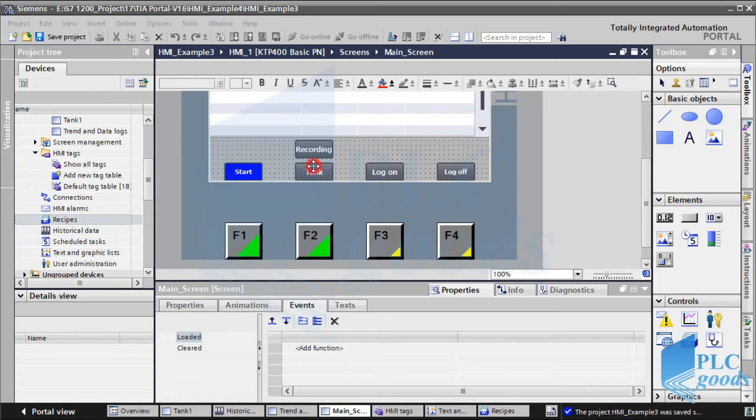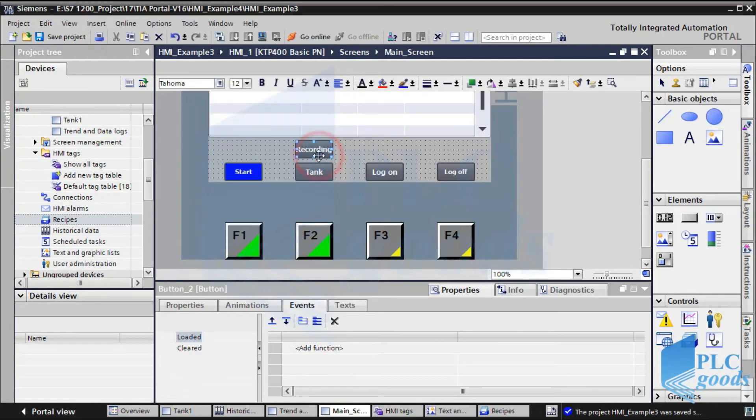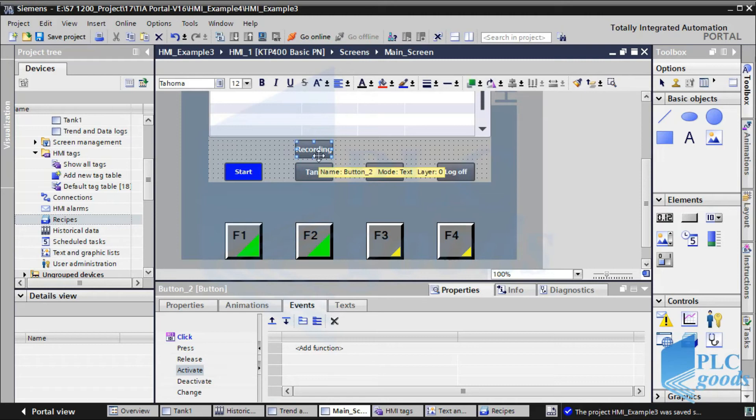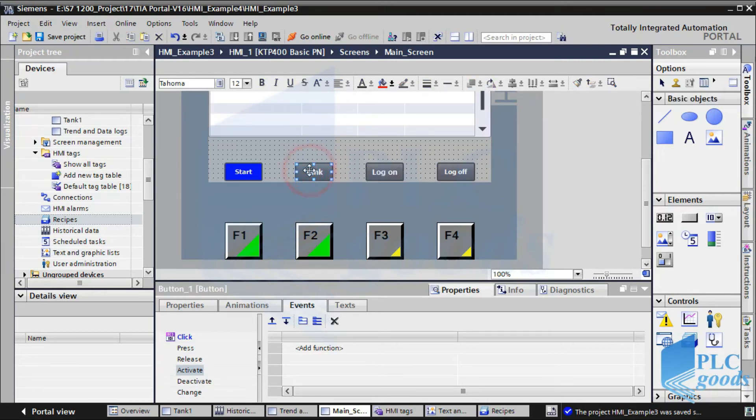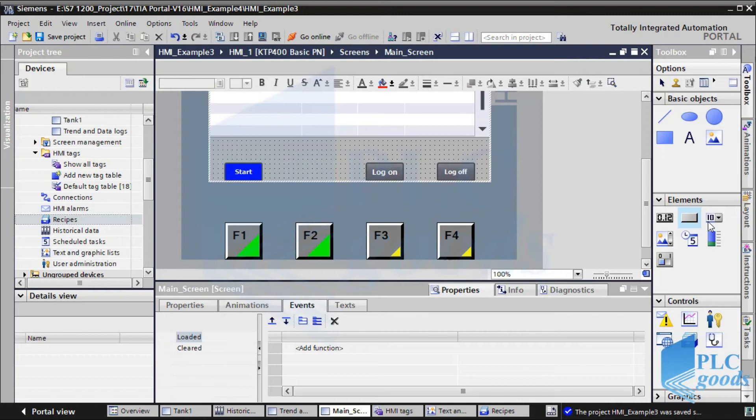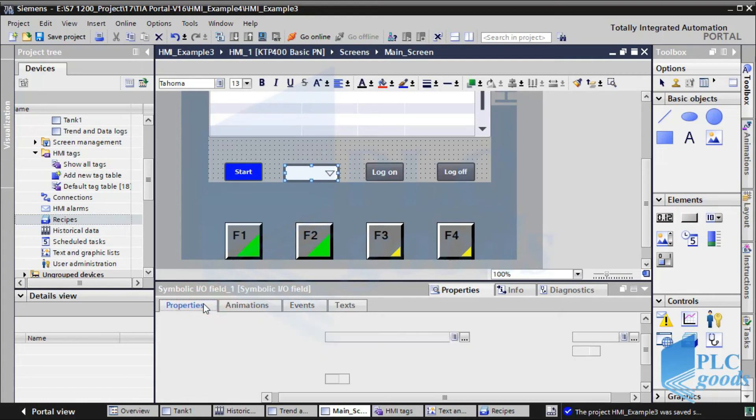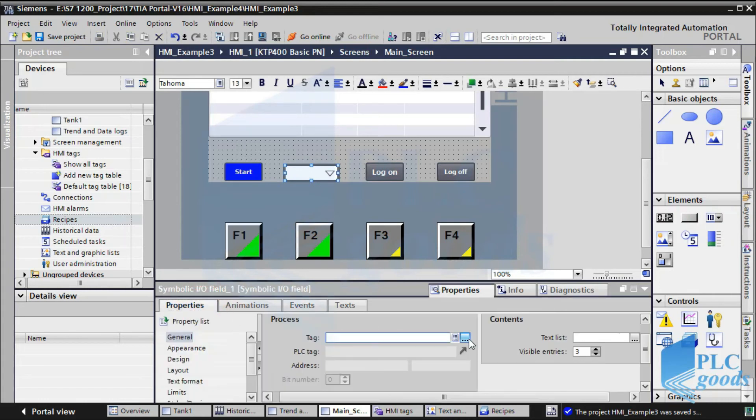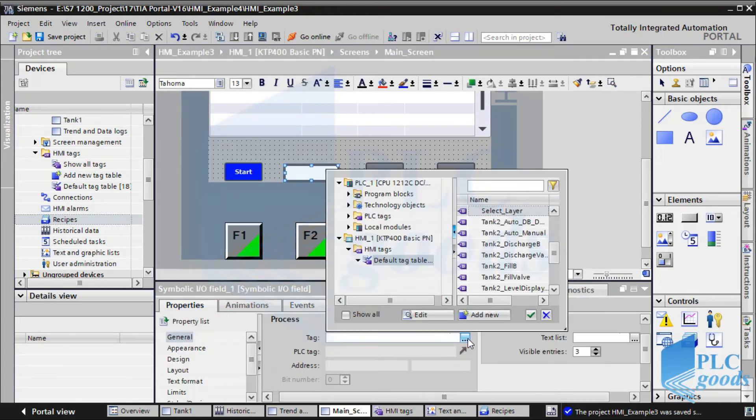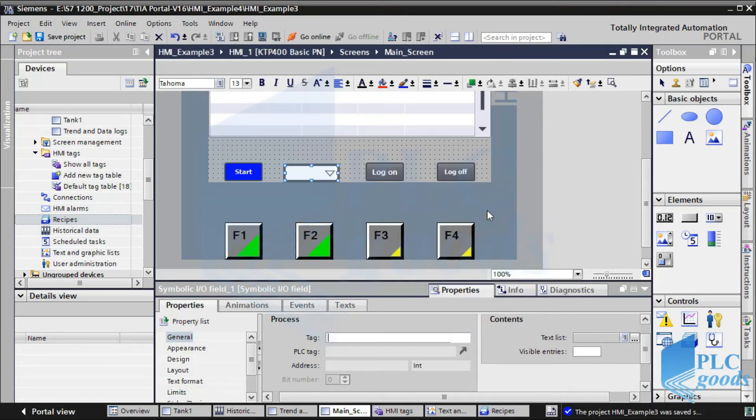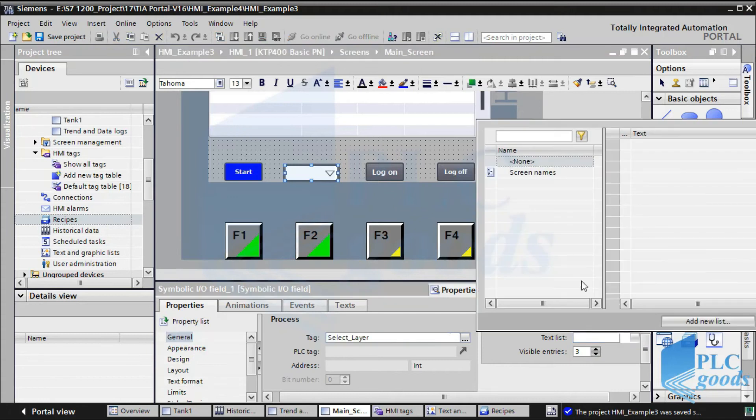Here, I have inserted another button to open the trend and logging screen which we have seen before. Now, we're going to use an IO field element instead of using a button to open each screen. In the inserted element properties, I use the defined internal tag. Also, I use a text list which has been defined before.